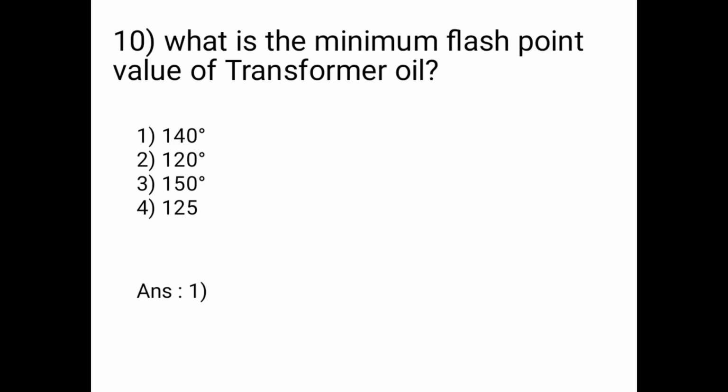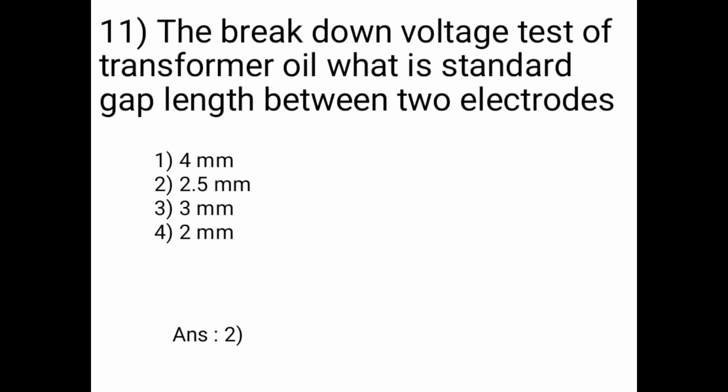Next question: what is the minimum flash point value of transformer oil? So 140 degrees is the minimum flash point value of transformer oil. Question number 11: in the breakdown voltage test of transformer oil, what is the standard gap length between two electrodes? 4 mm, 2.5 mm, 3 mm, 2 mm. So our answer is option 2, that is 2.5 mm.